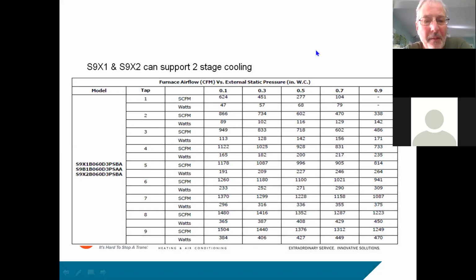And if you look, yeah, here's the one I wanted to get to. On the 9-speed motors, depending on the static pressure on the system, low speed, you can go from 277 CFM to 1376 CFM on tap 9. So when you're setting up air conditioning, you can either do the static pressure, look for the proper airflow, and change your speed tap accordingly. Okay, and that's an electronic speed tap, so it's done internally on the furnace.